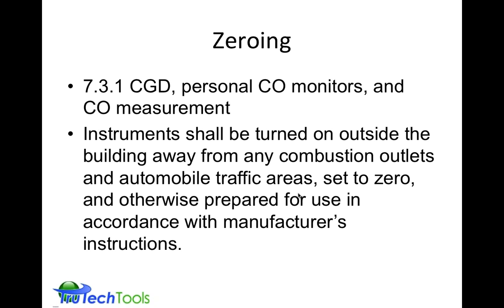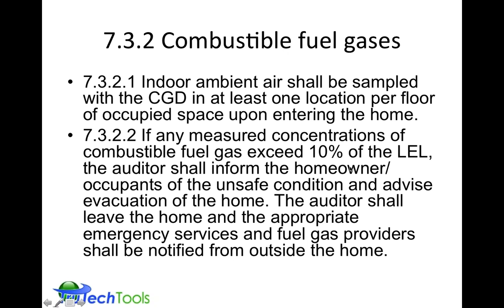The instrument should be turned on outside for zeroing. Be aware of any automotive traffic or combustion outlets, outlets for stacks or vents or things like that. The process for doing the testing, again, this is the how to, what to do, and how to do it. The combustible gas detector must be used at different levels of the home, at least one location per floor level.